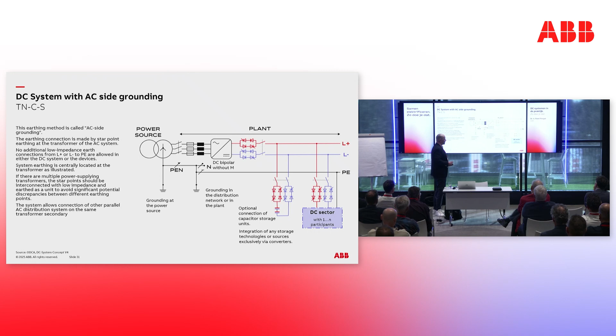One of the disadvantages: you need short circuit current interruption in both plus and minus pole. Because you can have a fault to the ground on the AC side, and you need to be able to operate or stop the short circuit current in both phases.